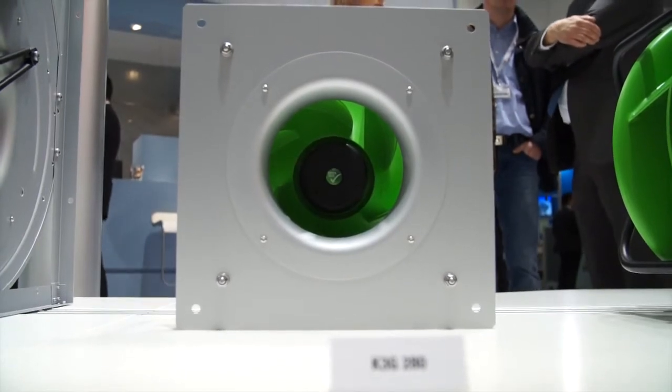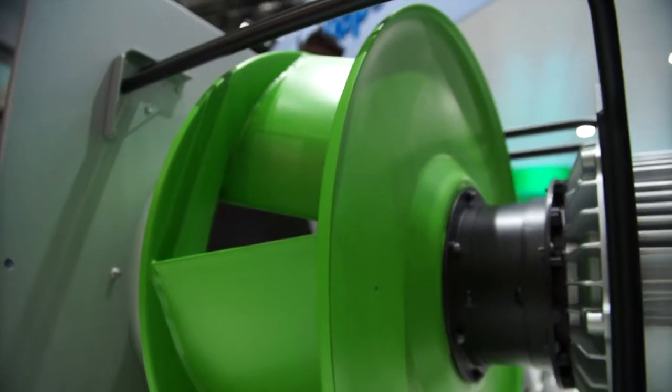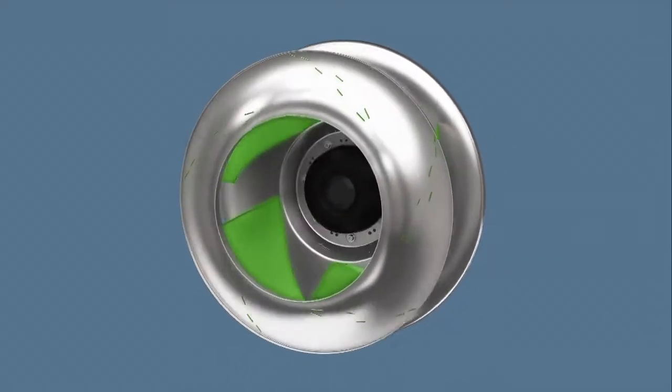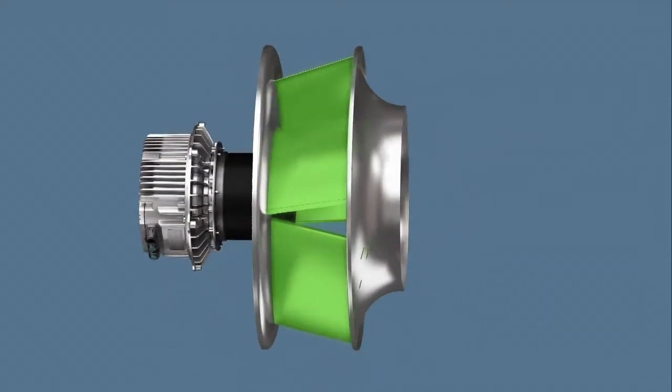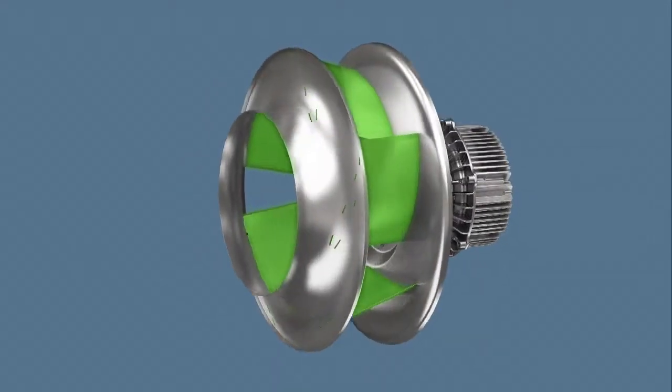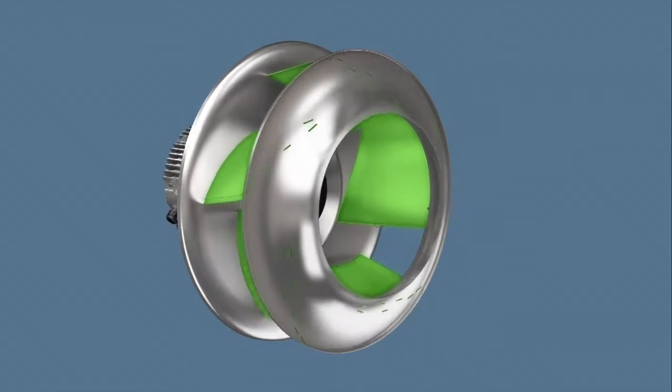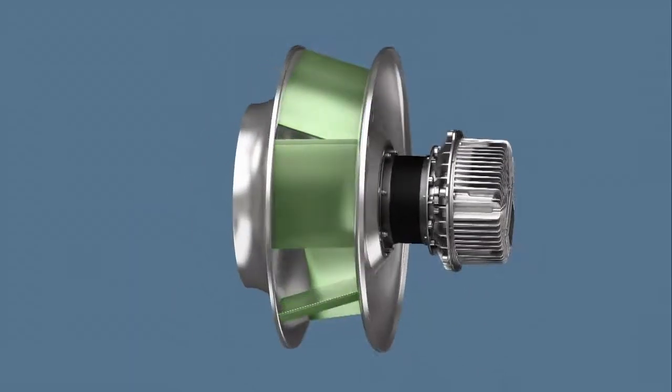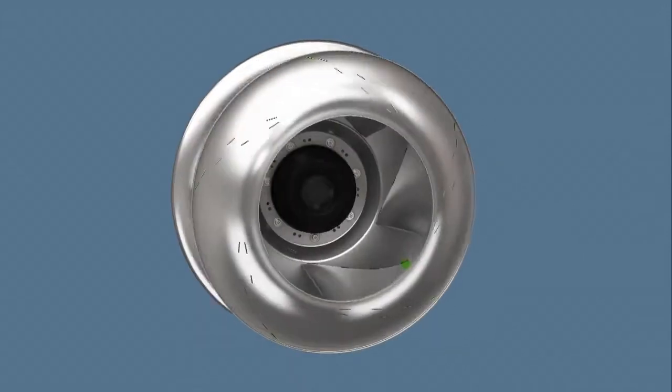The inlet nozzle was redesigned to perfectly match the impeller with its aerodynamically optimized blade channel. The new aluminium airfoil blades increased the efficiency by reducing the weight of the impeller. Pressure losses at the inlet were further reduced and the outflow behavior was improved.